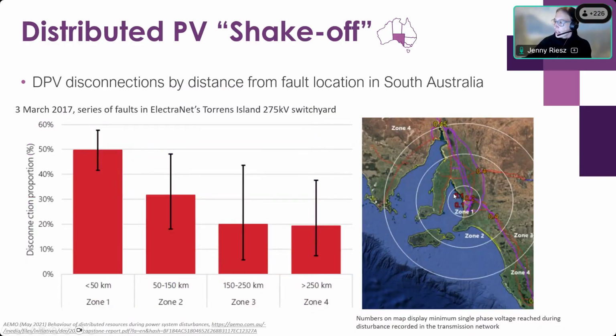You can see here the minimum voltages measured on the network right in the middle of the South Australian region, and these are our estimates of how much PV looks like it disconnected or was shaken off by those faults. In the immediate vicinity, right where all of the PV is installed, around half of the PV we estimate was shaken off, and even out to most of South Australia we still see about 20% of PV systems shaken off.